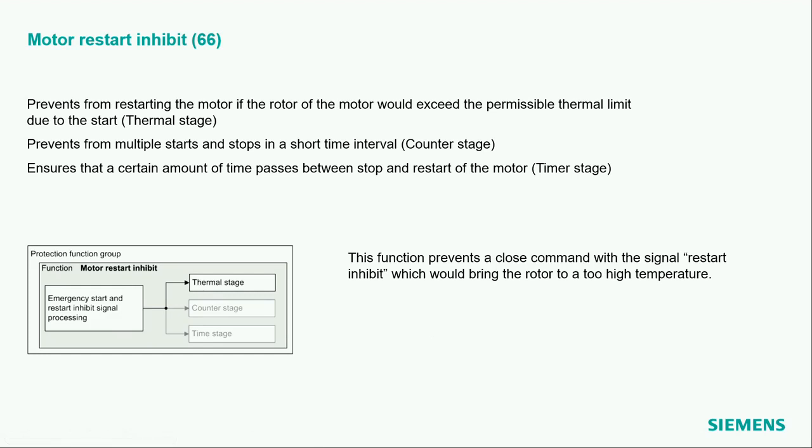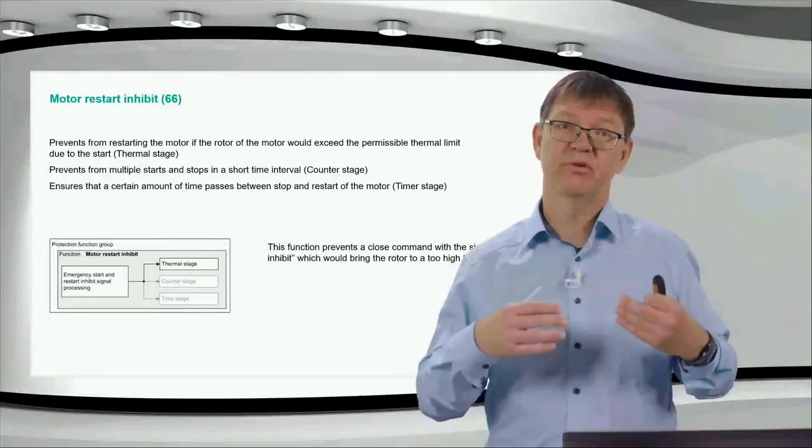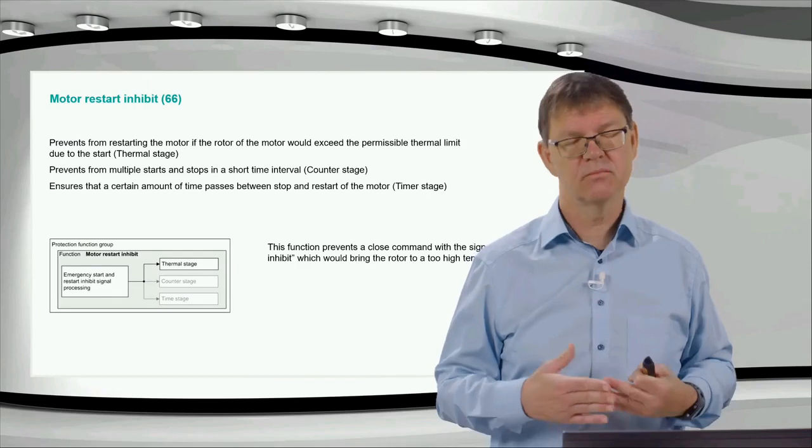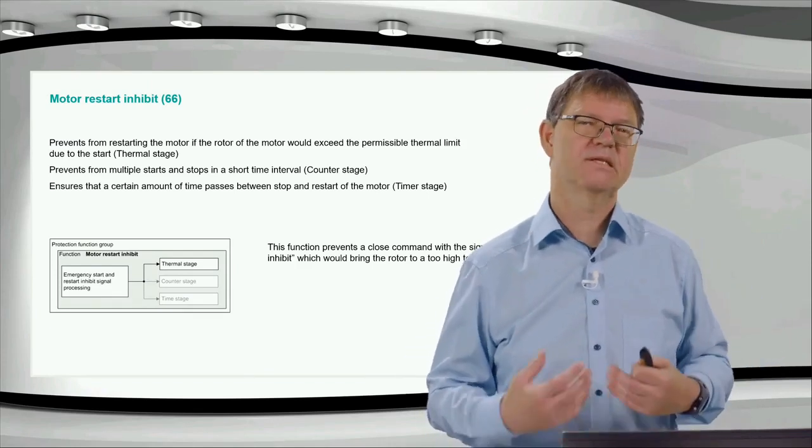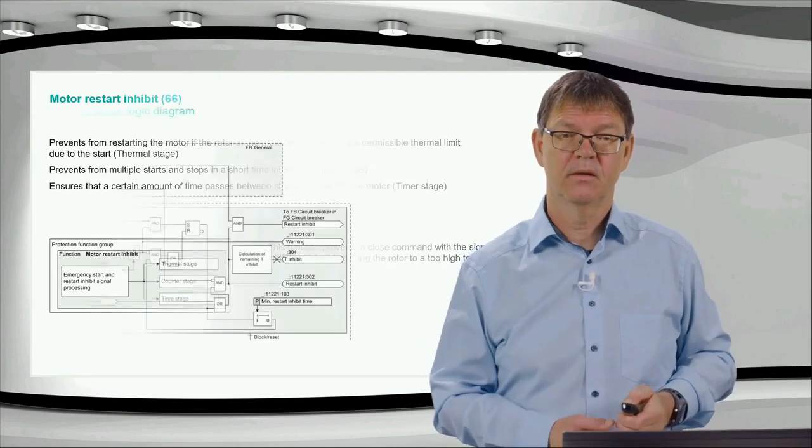Again, this function does not trip. This function just prevents the restart, a restart inhibit, so a blocking signal, which prevents a restart. So this function becomes active after the motor has been switched off and the motor is at standstill here.